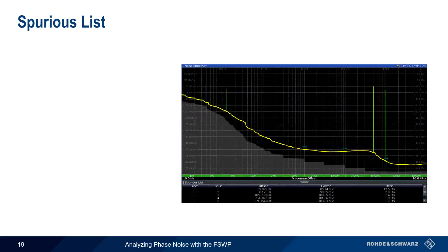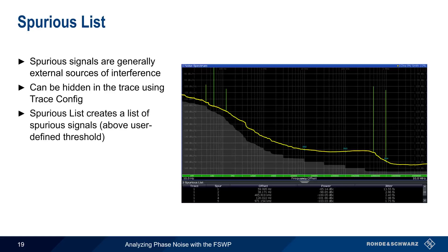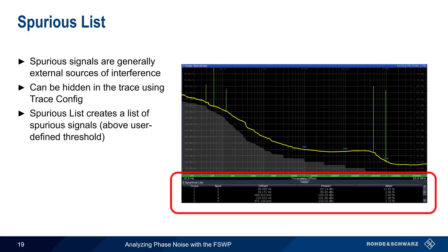Spurious signals are external sources of noise that cause peaks or spikes in the phase noise trace, and we showed how these could be hidden using the Trace Config menu. The spurious list measurement, on the other hand, creates a list of spurs above a user-defined threshold. The results are reported per spur and include the offset frequency and power of the spur, as well as the measured jitter.